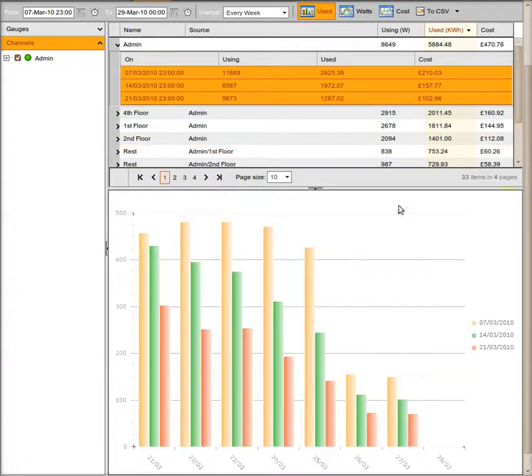Takes a little bit of time. There you go. You can see how the client's managed over the period. I mean, quite a huge reduction on these Mondays, bigger on the Tuesday, even bigger on the Wednesday. I mean, he's now actually even got the weekend loads to come down. In fact, we've reduced consumption from about 2600 kilowatt hours per week down to 1300, over half the load, and this graph, I hope you can see, illustrates that.